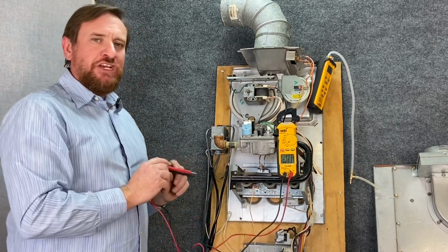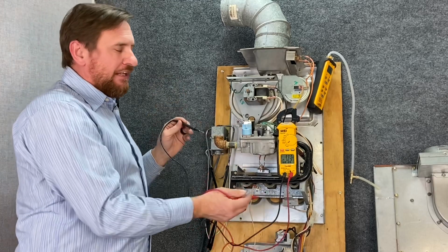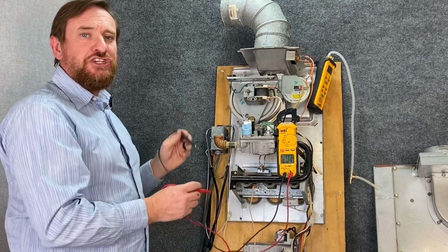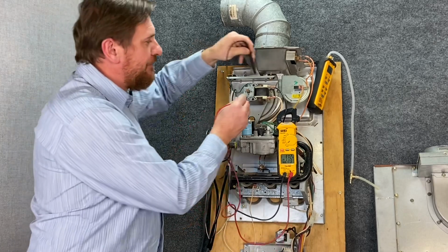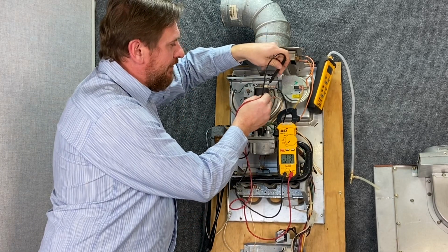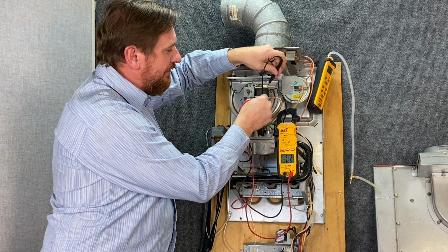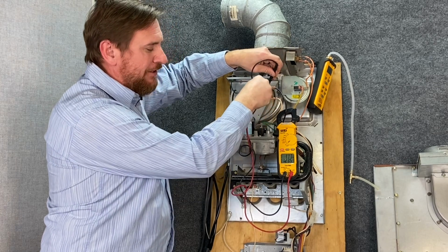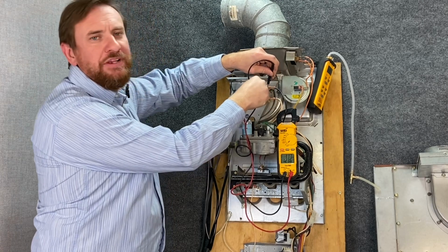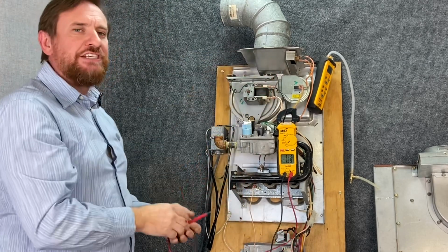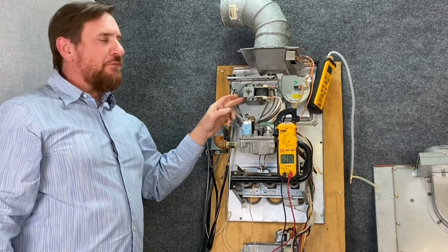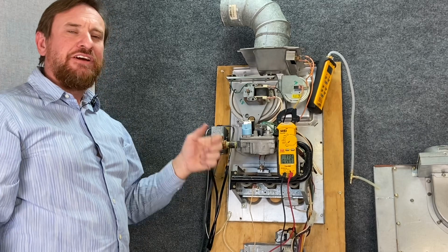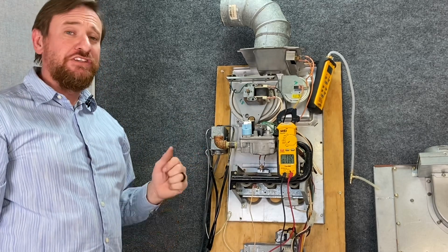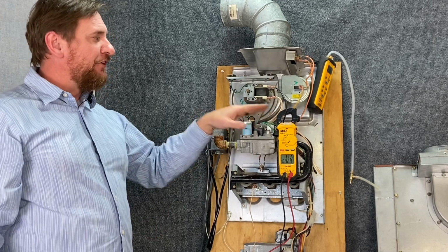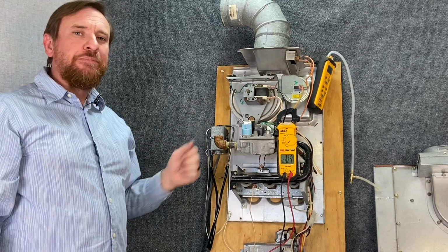In addition, I want to check to make sure I have the proper voltage to my motor. Low voltage or high voltage can tell you have some other issue either with the system or the power in the house. So I'm just going to move my leads so I get good contact with the metal, and here I'm showing 123.6 volts. So that's good. I'm within the range of voltage needed for this motor. The motor has printed on it what the maximum amps are, and usually a voltage range as well, which is usually 10% of rated. So we know we have the proper volts, we have the proper amps. Now, is it pulling the proper vacuum? So let's check that next.